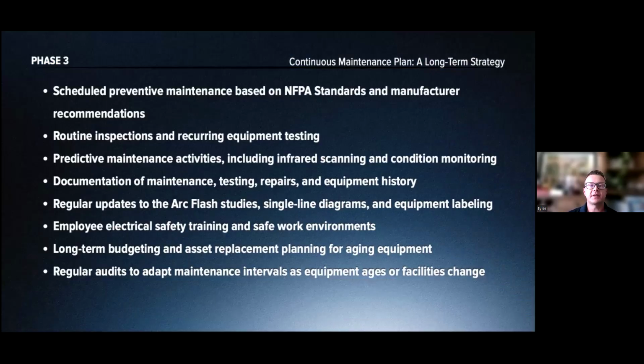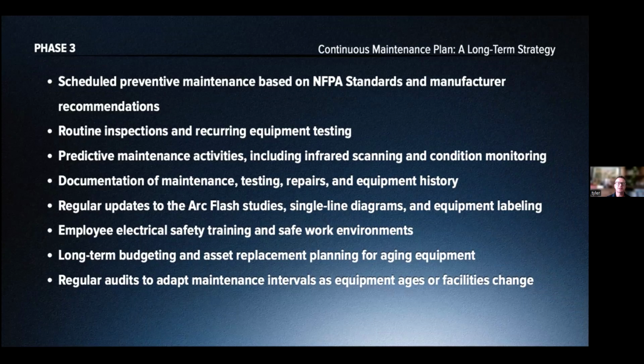Phase 3 is scheduling preventive maintenance based on NFPA standards and manufacturer recommendations, as I talked about earlier. You want to go off the standard, but also check your manufacturing equipment for what they recommend for testing, so we can be in alignment and be the most practical.